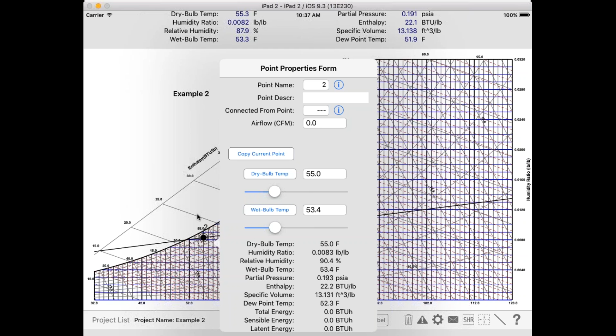Okay. So as you can see, as I move this point, it moves along the line, which is quite convenient. So I'm going to move this point along the line until I hit 55 degrees dry bulb. There I am. So I'm going to double click this point, and you're going to see now, here are the properties of that point that I created, and it followed the sensible heat ratio line. So therefore our answer is the enthalpy is 22.2 BTU per pound. So this is an example of how to use the sensible heat ratio line, and we got a number of questions during registration on this. So this is pretty powerful, and I'm going to show you a number of other examples on how to use the sensible heat ratio line.